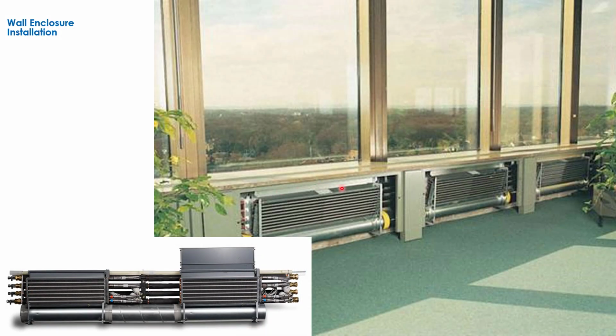Beams also can be mounted across the wall. Often when you do that, the lines are dropped down through a corner furring or brought up through the floor slab to these units. Often the enclosure lines up with the window mullions, whatever the style is. And one of the ways you can pass across multiple chill beams around the perimeter is to have the chill beams supplied with a piping rack like you see here. You can see this is a 4-pipe system. And the water was drawn off of these things so that it could pass on to multiple chill beams on the same facade of the building.